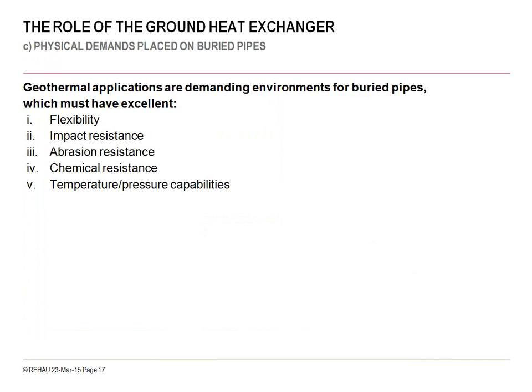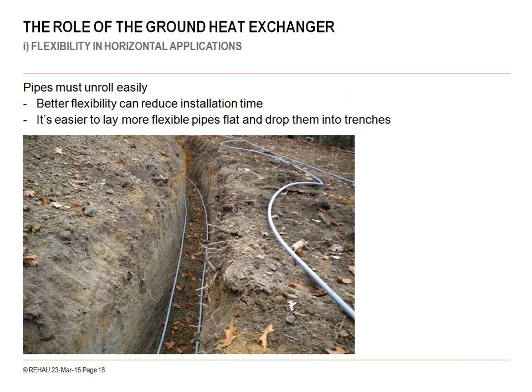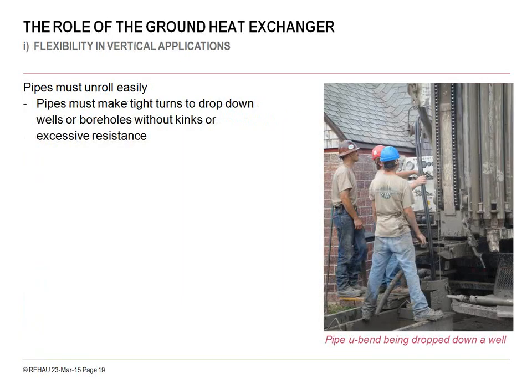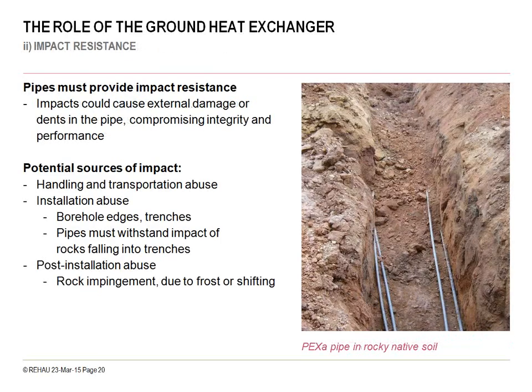I'm going to talk now about some of the physical demands that are placed on these piping systems. A little bit on the flexibility, impact resistance, abrasion resistance, 2 important factors there. Chemical resistance, and then temperature and pressure capabilities. On flexibility, you can see this is with a PEX-A pipe that provides very good flexibility for being able to uncoil the pipe and get it into a horizontal trench. You want pipes that are going to be unrolling easily for, in this case, high-density polyethylene going into a vertical borehole. You want to have flexibility, but at the same time you want to have a stiff enough pipe that you're not getting into kinking of the pipe doing insertion down a vertical borehole.